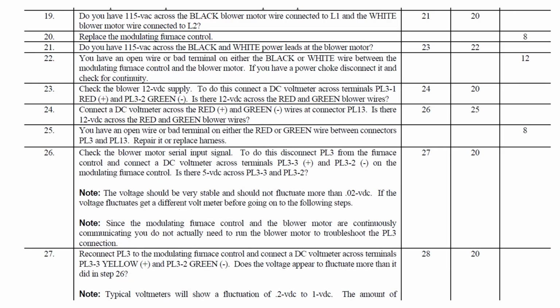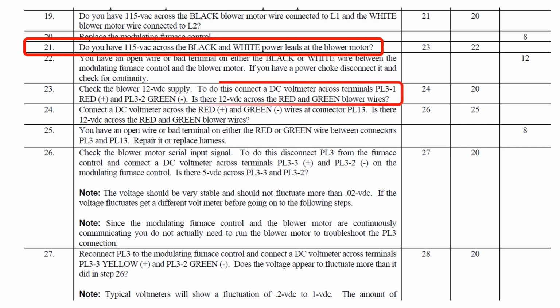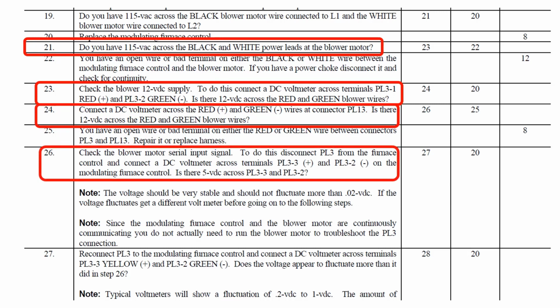This again is out of the troubleshooting guide to follow for an ECM motor that is faulted out. They will ask you, of course, if you have your 115 or high voltage to the electronics. And then they will go through checking the various wires on the communication plug to make sure that you have the correct DC voltage communicating to the motor.